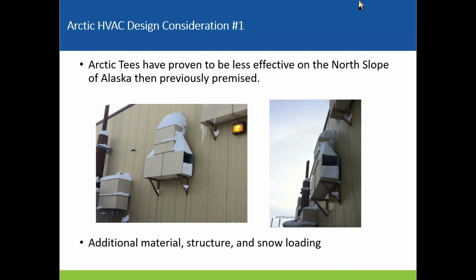Throw in some Arctic design considerations. Arctic tees really have proven to be less effective than originally premised. As you can see, they collect a bunch of snow, adding more snow loading onto the structure, and they've had to add additional support for these. Really, all we're seeing anymore is 90-degree downturn hoods. That would be my recommendation moving forward.